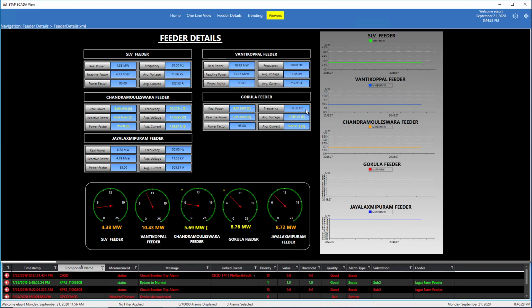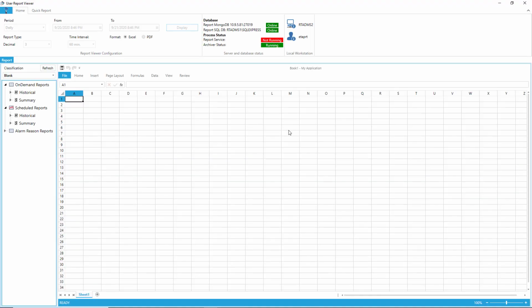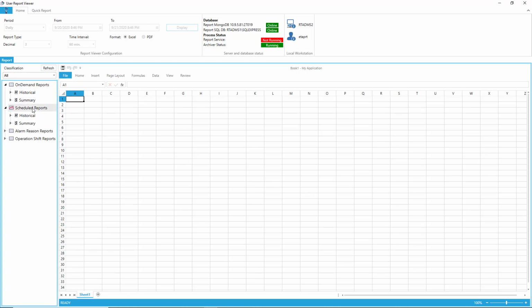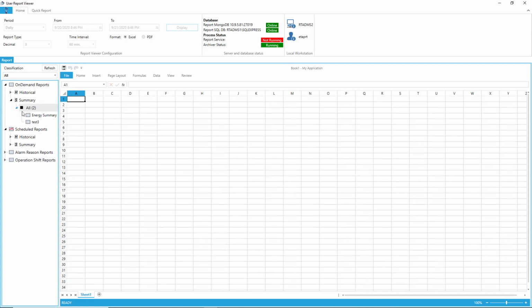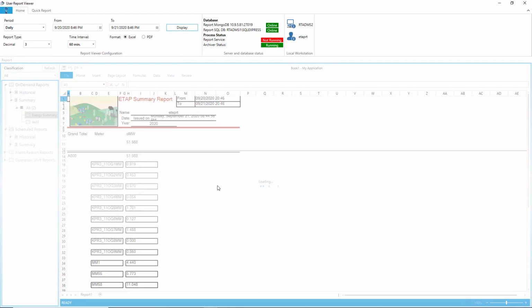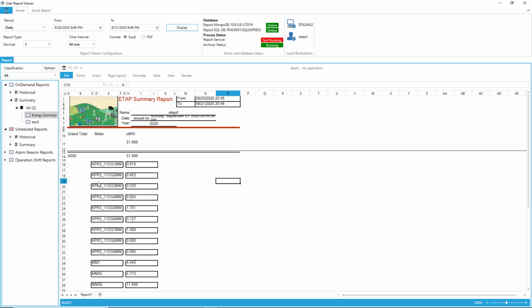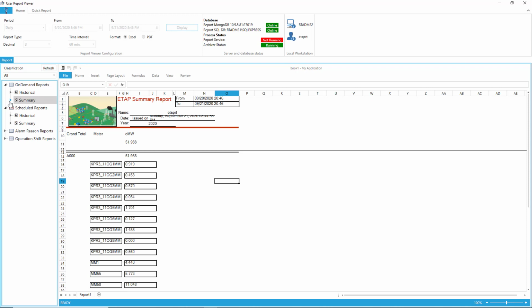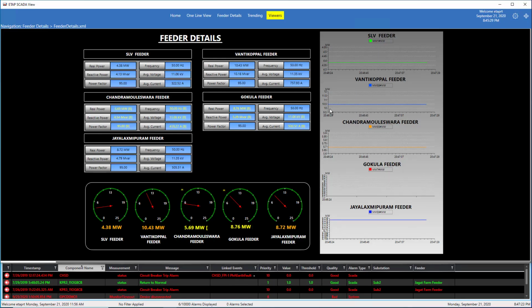And one more thing that's kind of nice is the report viewer. The report viewer is available in an enterprise solution. However, from the substation itself, I can come in here, select all the reports, and go look at, for example, an energy summary, display the report, and get a very friendly Excel-based report with the different values and energy consumptions. If I wanted to get alarm reason reports, so if there was an alarm and we want to know the cause of the alarm, you would generate an alarm reason report. The reports are historical, can be summary reports, can be scheduled reports, and can be emailed directly from the iSub system. So it's a very nice tool to understand how the substation is behaving.